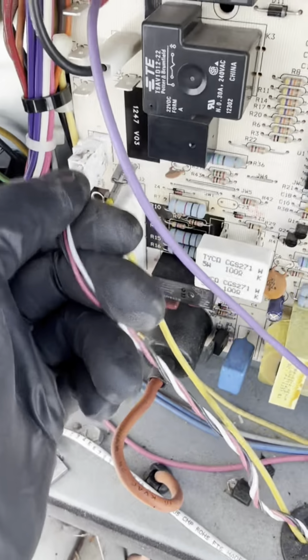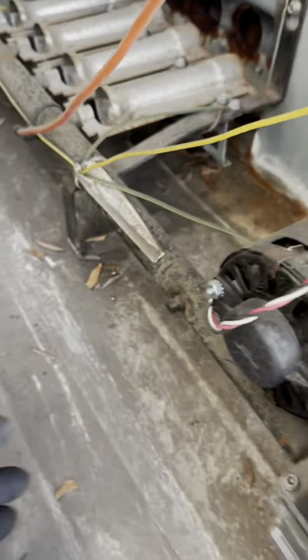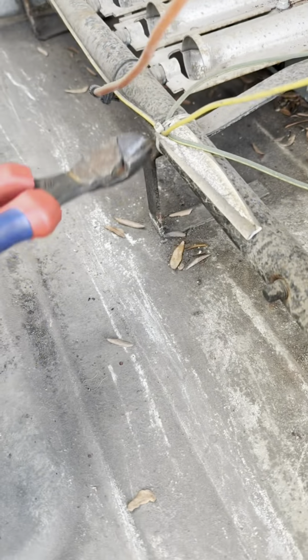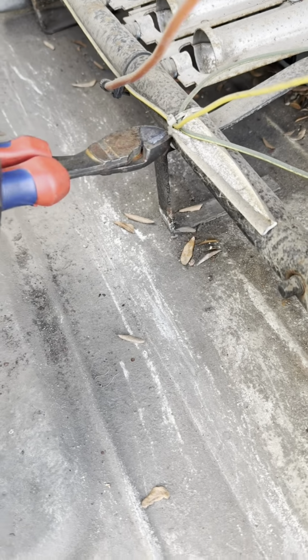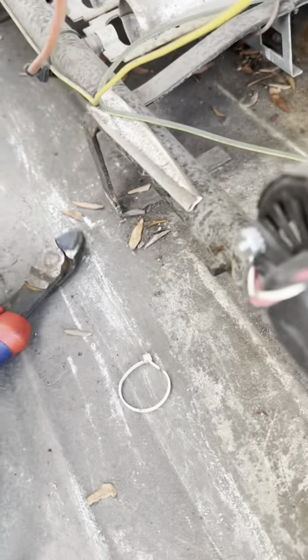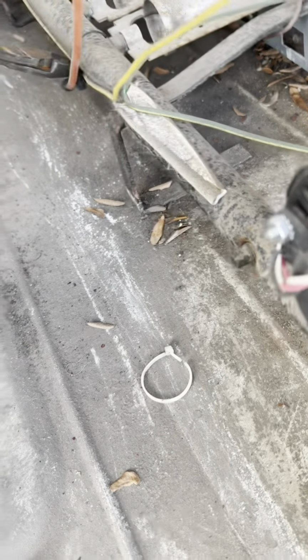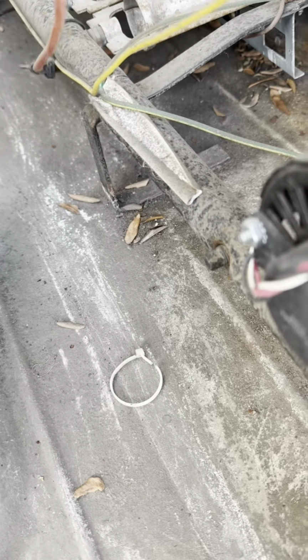Remove the inducer RPM switch and the inducer power off the board and send them down. Undo all the wire ties off the burner so we can take the burner off. I am replacing the flame sensor and the igniter.